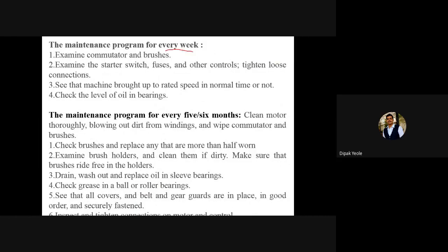Examine the commutator and brushes. Examine the starter, switch, fuses and other controls, tighten loose connections, see that the machine is brought up to the rated speed in normal time or not, and check the level of oil in the bearing. And the last point, the maintenance program for every 5 to 6 months. So this is for every week and this is half yearly, one can say.